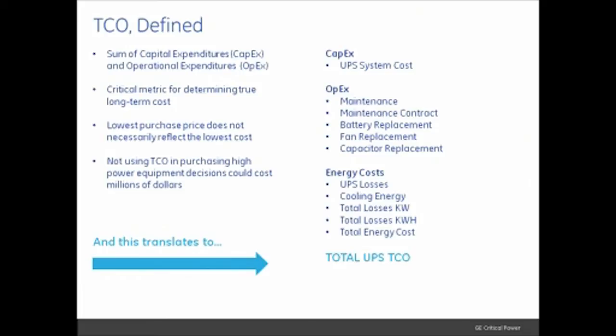The TCO is the sum of all your capital expenditures, which can also include installation, and the operational expenditures, which include your maintenance, battery replacement for UPS, fan replacement, capacitor, and other consumables within the UPS. Another key part of the OPEX we've broken out on the right-hand side of the screen is the energy cost: the UPS losses cost so much, and then you've got to extract that heat out of the data center. So you're looking at several different items you need to use to calculate your TCO.